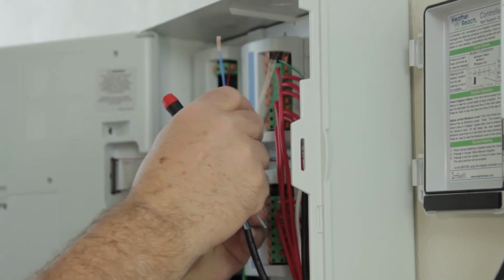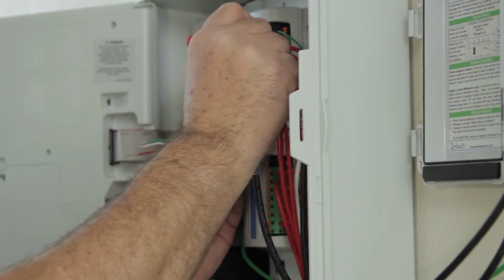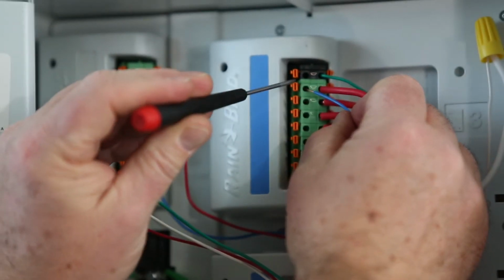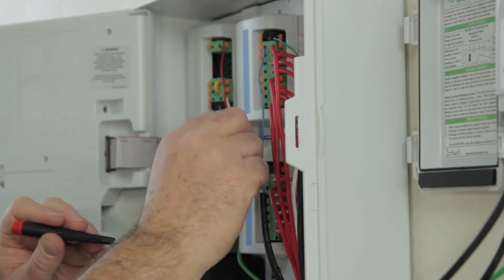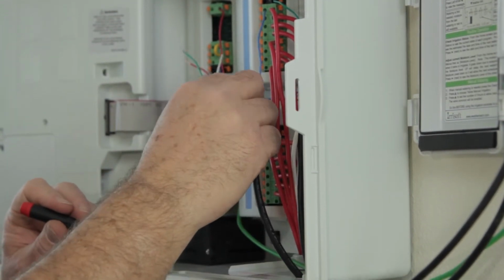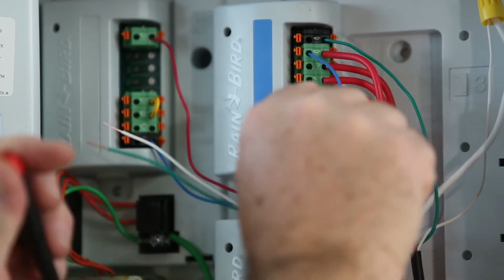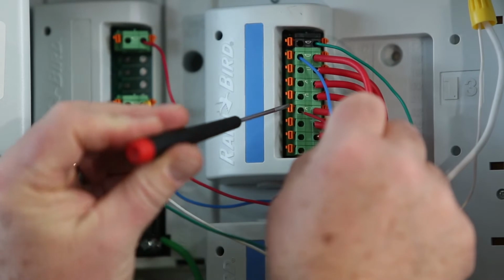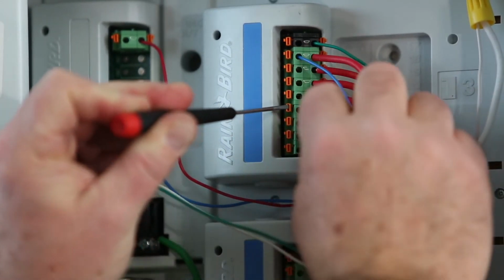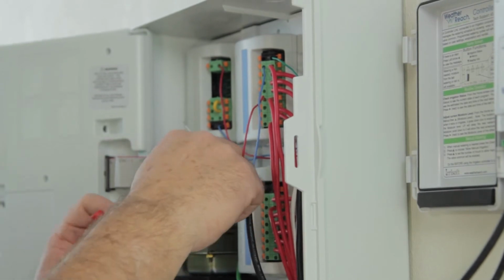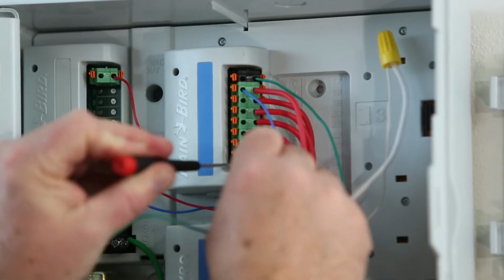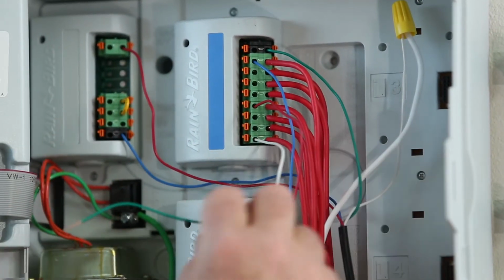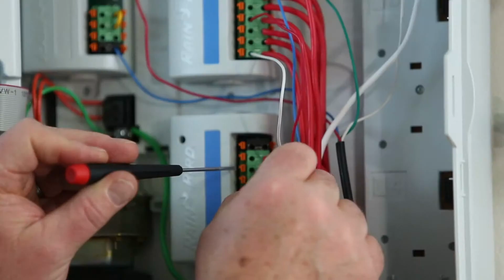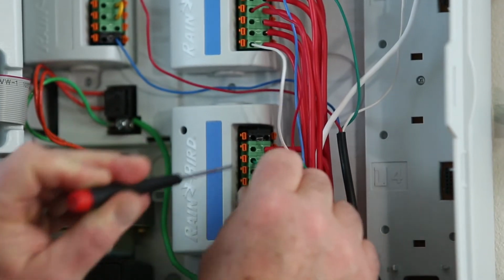In this example, we learned earlier that station 1 is the first station of program A, so the blue wire goes to station 1. Station 5 is the first station of program B, so the red wire connects to station 5. Our white wire goes to station 8, the first station of program C. And the green wire connects to station 10, the first station of program D. If you are not using all programs, leave the wire unconnected.